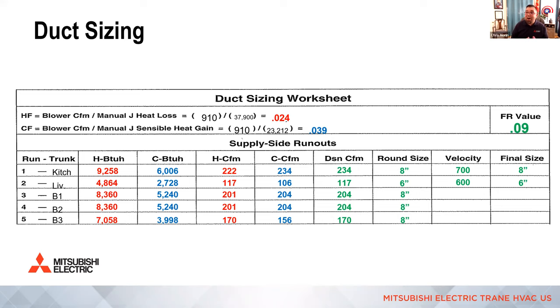So keep in mind, this is not a definitive number here. It's your application of the duct system and the map when it comes to designing the system and what's supposed to be installed. This duct sizing worksheet and an actual drawing of the floor plan with the trunk and branch, right, is what typically goes to the code inspector in order to verify that this design matches what was installed. All right. Now, if you're using some software like Wrightsoft or some of the other ones, some of that's built in and it actually does the drawing for you.